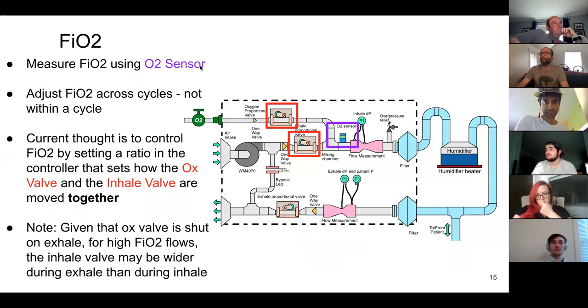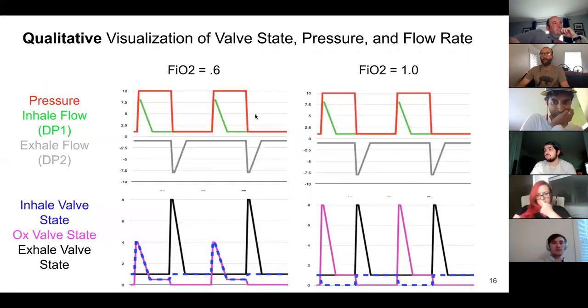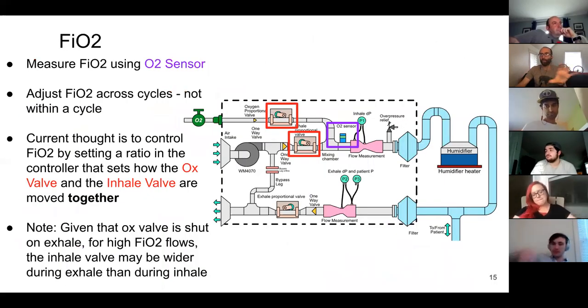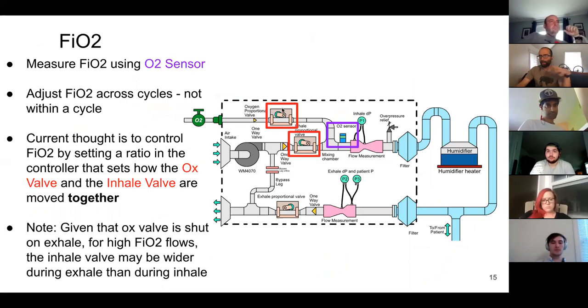Okay, so then oxygen control is an independent state, but it's really related there. And I think to do that, I'm gonna skip the pneumatic slide and talk through representative figures essentially. So coming back to here for a second, we're going to treat the oxygen and the air valve as one valve during inhale. So assuming that they were perfectly linear and running off the same pressure source, then it would be exactly proportional, but they're going to be at different pressures and different valves with different characteristics. So we're going to have to apply some correction to essentially get them to be linear and proportional.